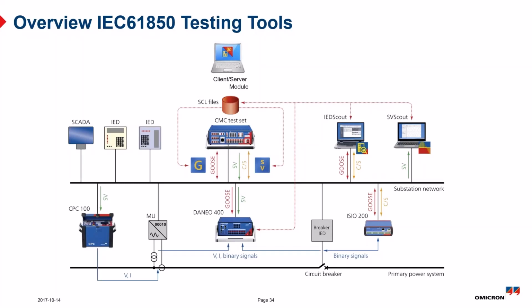So testing a 61850 substation is a bit more complex. What we've got here is that we don't have test switches. We can use a conventional analog input and output, but this shows what our offerings are. This is our same services: GOOSE, sample value, client server. So we use our CMC test set.